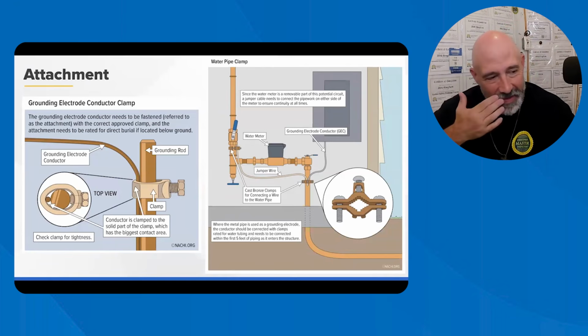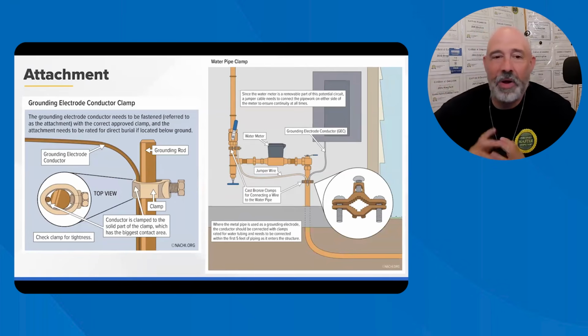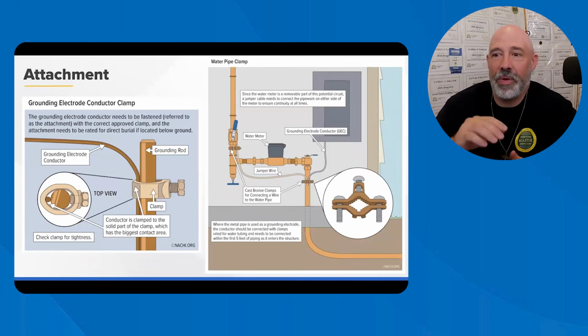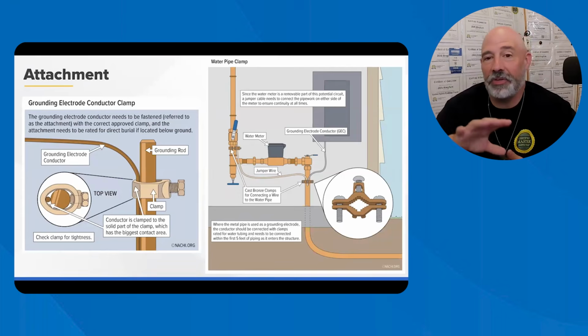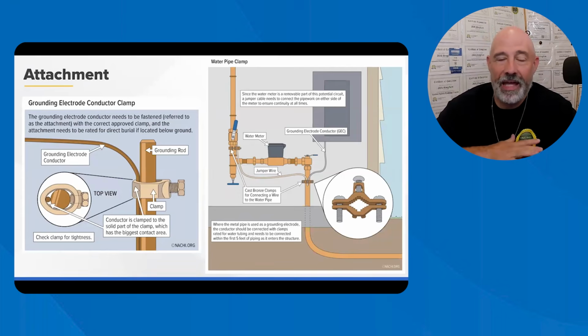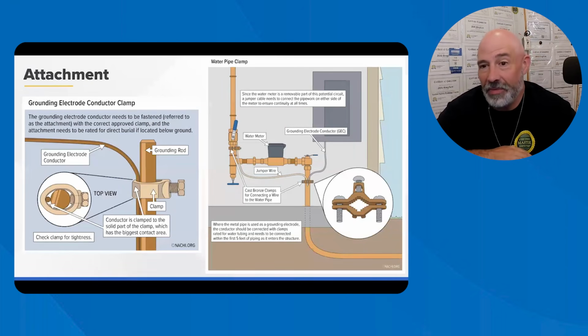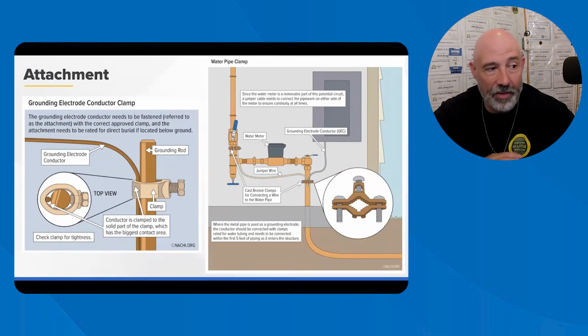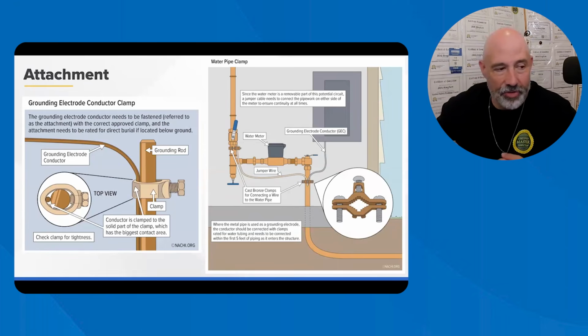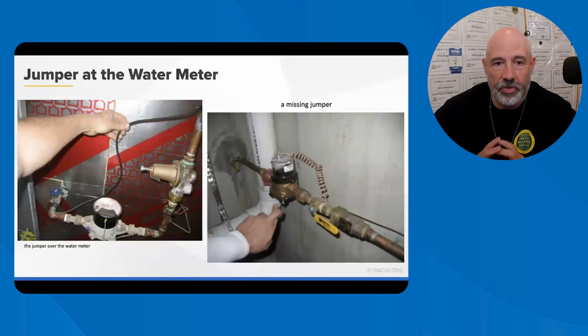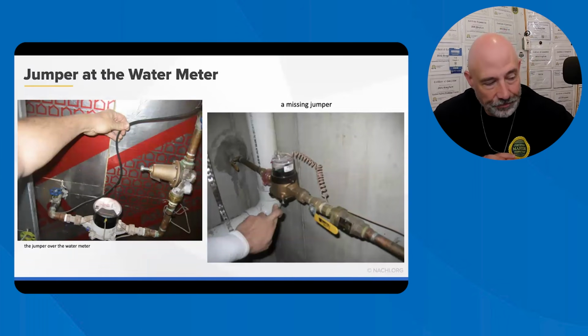It's not supposed to be underneath that, whatever. Let's not go there. When a metal water pipe is used as a ground electrode, the connection must be made within the first 5 feet of where the pipe enters the home. Because water meters can be removed, a jumper wire must be over that water meter. And you can see the jumper wire in that illustration right there. And again, something you should be looking at, especially if you see this quite a bit. And I do a lot of new construction, so I don't see this too often anymore. Kind of sad. Kind of miss those old houses. So that jumper wire is definitely something that you should be looking at.